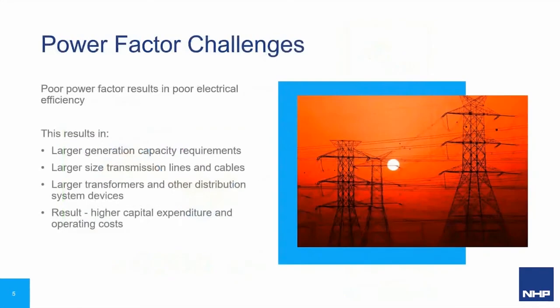So first, let's talk about power factor. Poor power factor results in poor electrical efficiency. This can result in larger generation capacity requirements, larger size transmission lines and cables, larger transformers and other distribution devices, and as a result, it means higher capital expenditure and operating costs. This is also why energy providers are now passing on penalties to large consumers of reactive energy.